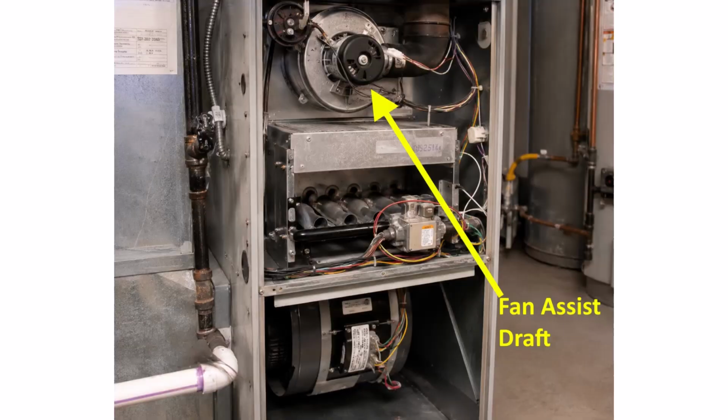people used to call mid-efficiency furnaces, and it's where you've got a little draft inducer fan right at the furnace. Typically, you've got to take the front cover off, but you've got a little inducer fan, and then it takes the exhaust gases out of that appliance, kind of pushes them a little bit, gives them a little head start on getting up and out of the house, but you are going to have a metal vent coming out the top of your furnace. And boilers would have those too. So that's option number 2.